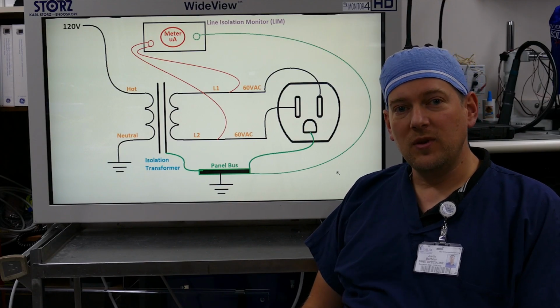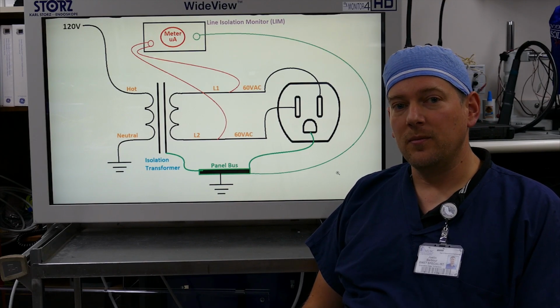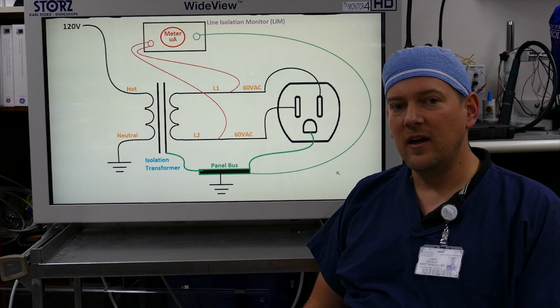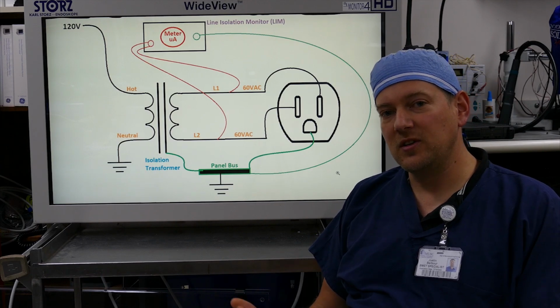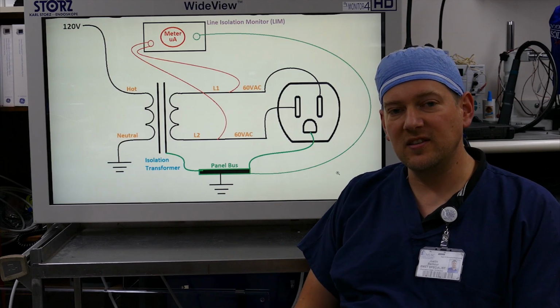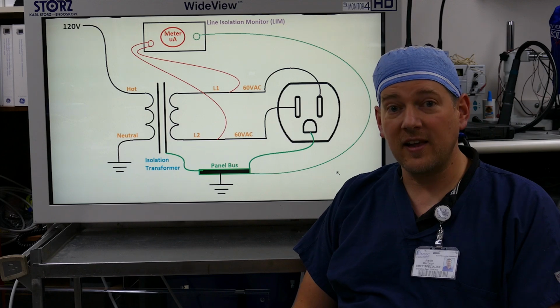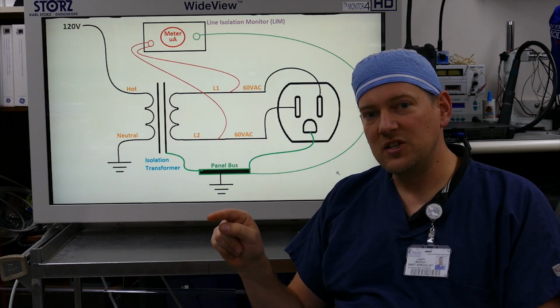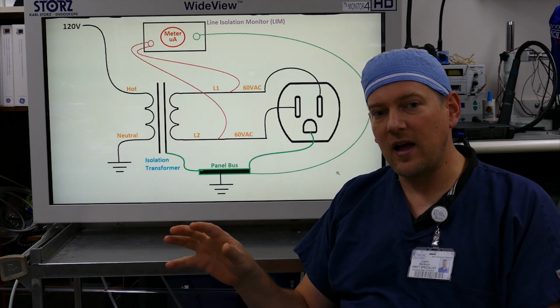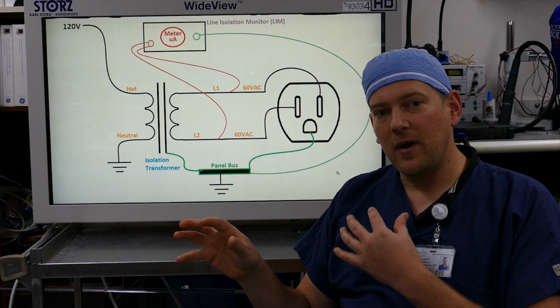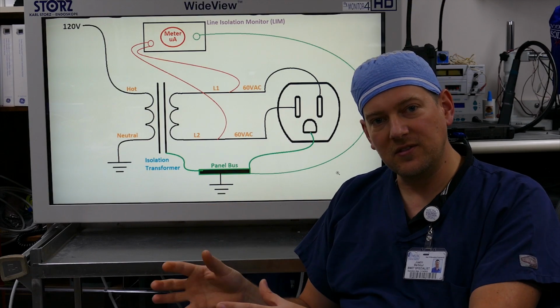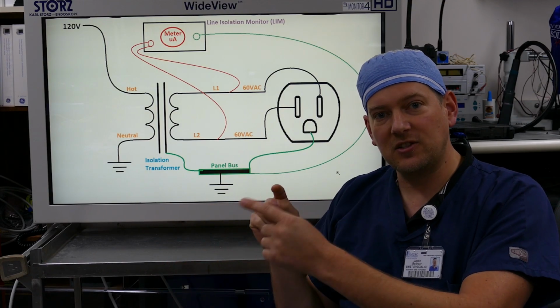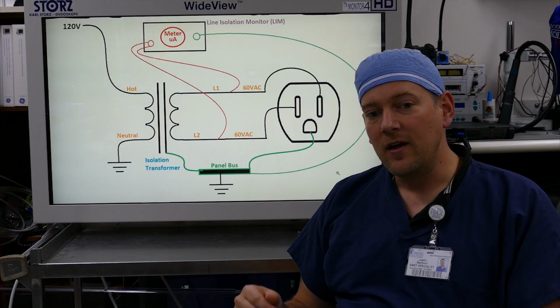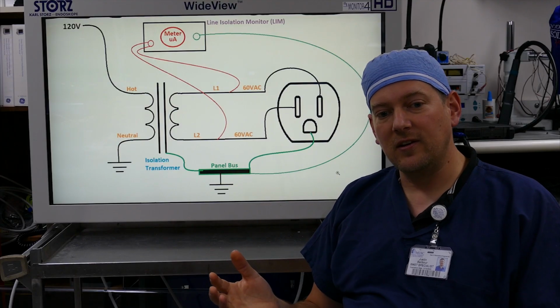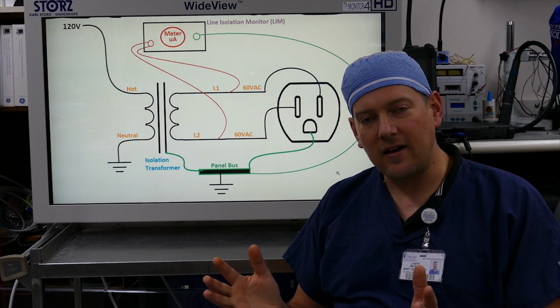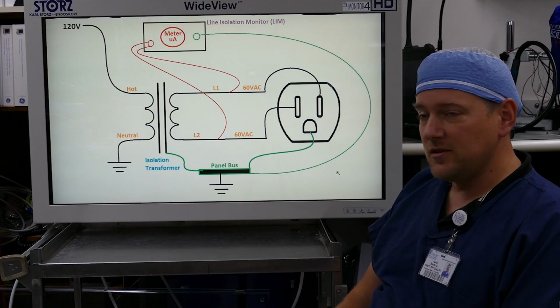When staff tells you that they've been shocked in an operating room, usually what you'll find is there'll be static buildup, especially since the room is full of stainless steel equipment, often on nylon casters. So when staff reaches down and they touch a stainless steel object, they are at a higher potential than the stainless steel, and there'll be a static electricity arc between their finger and the object. Often staff think that they're getting electrocuted, but it's not. That is an isolated power system.